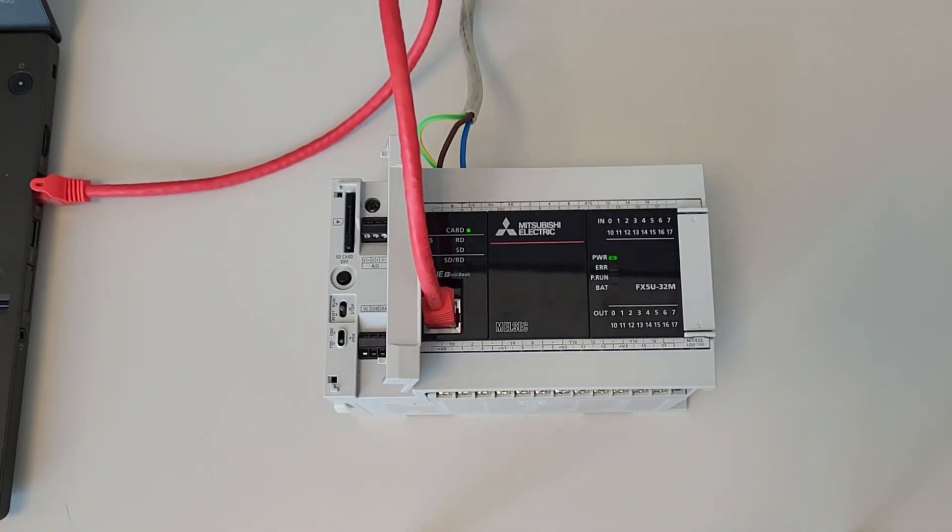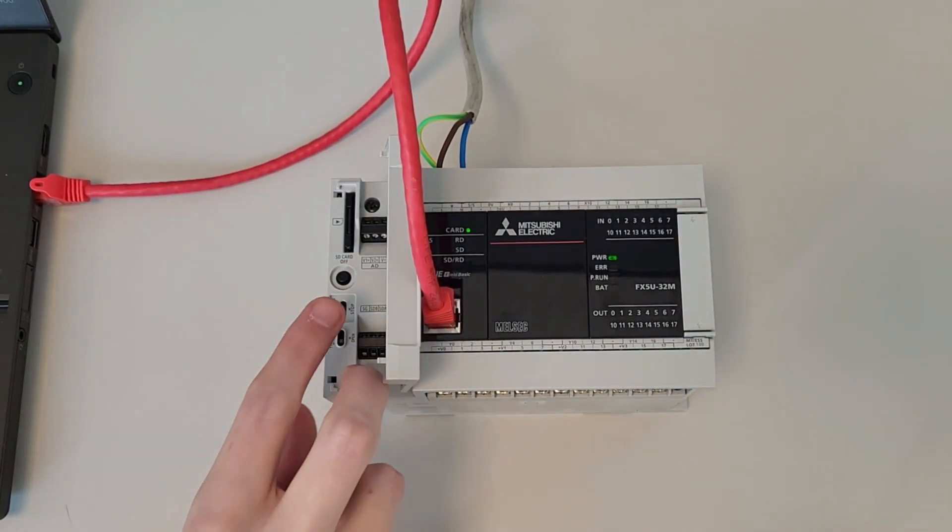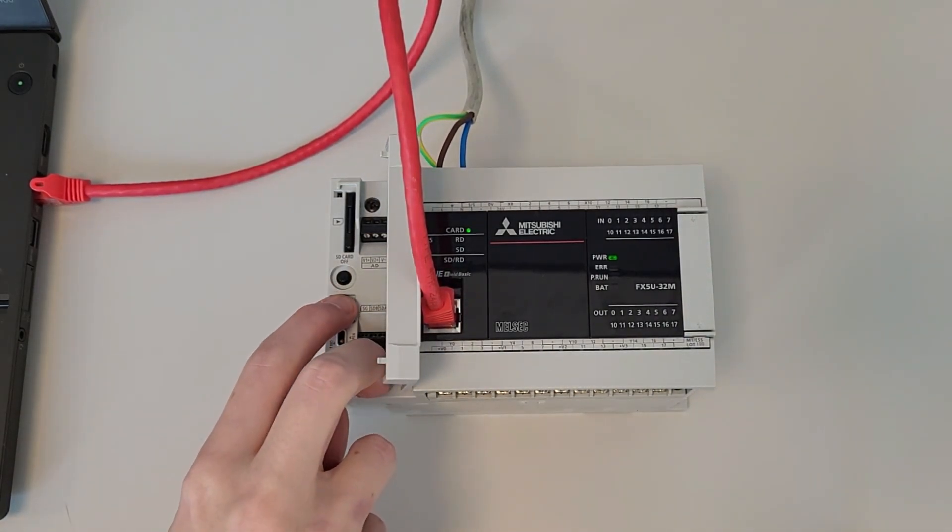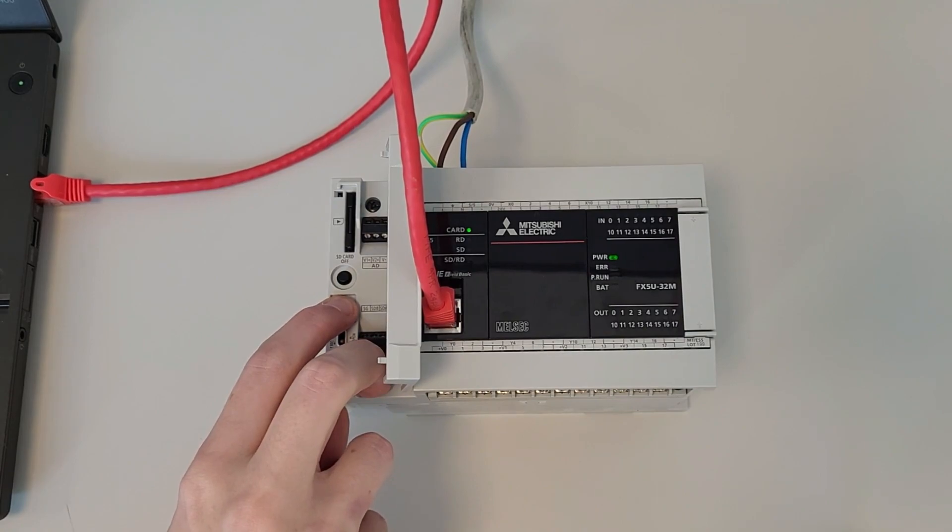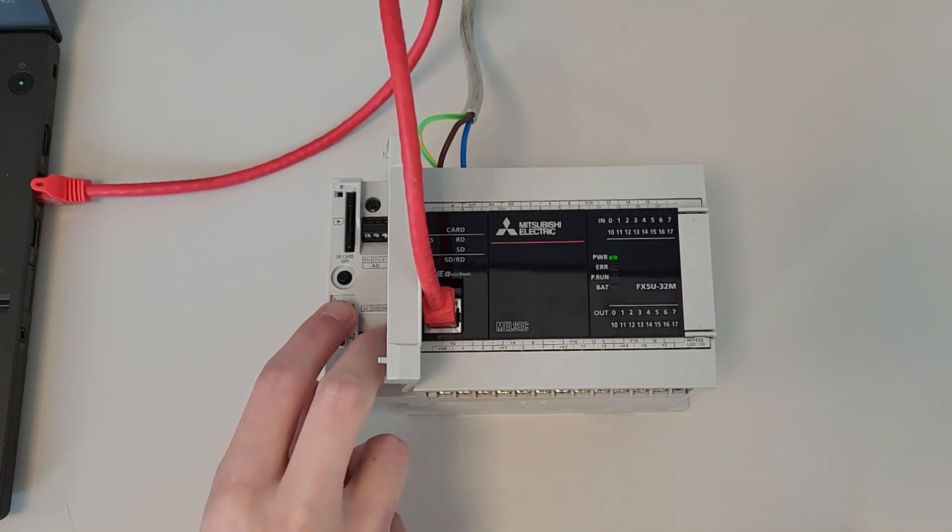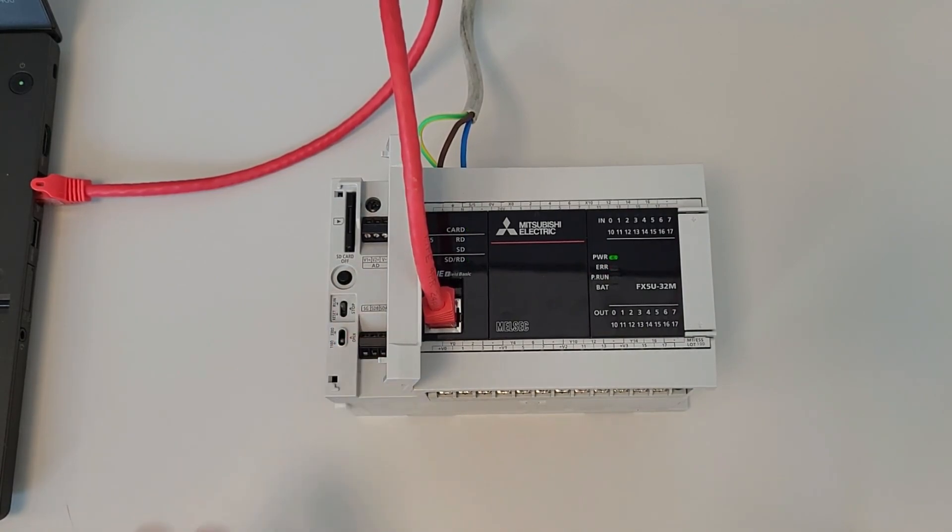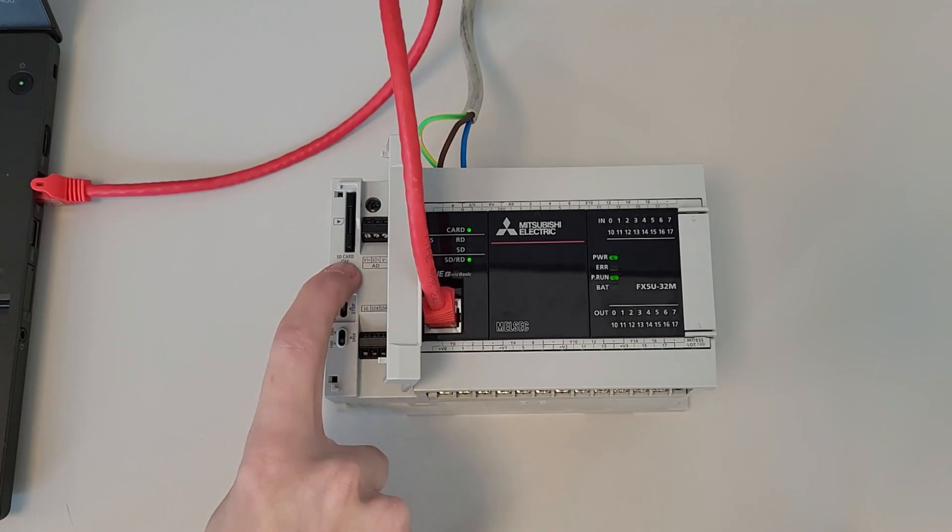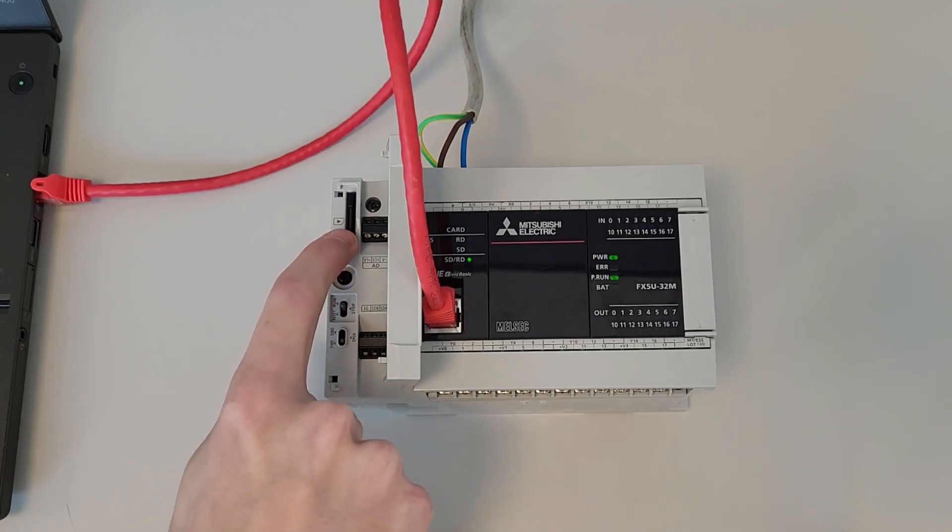When we turn it on we have to maintain the selector on reset for three seconds and then we can move it to stop and run. After a couple of seconds the PLC will go to run with the new files. Press the button SD card off to remove the SD card.